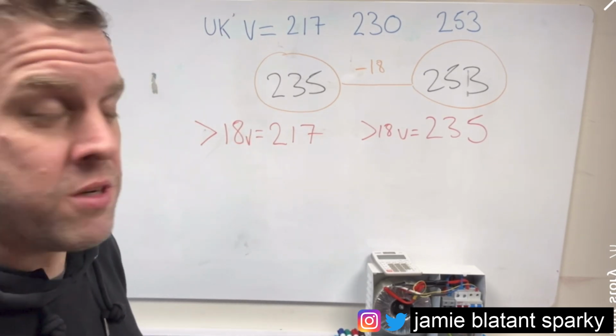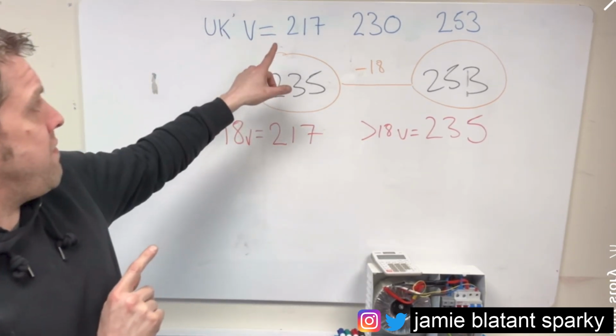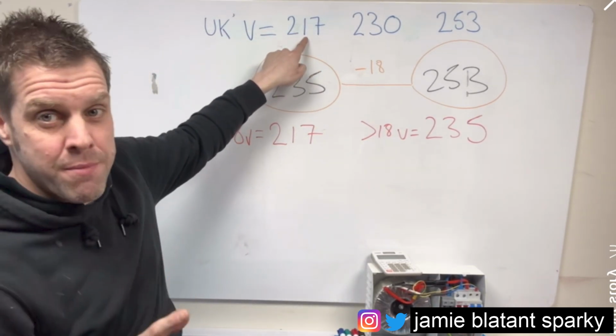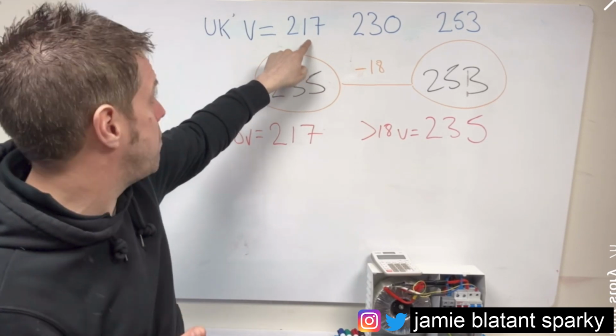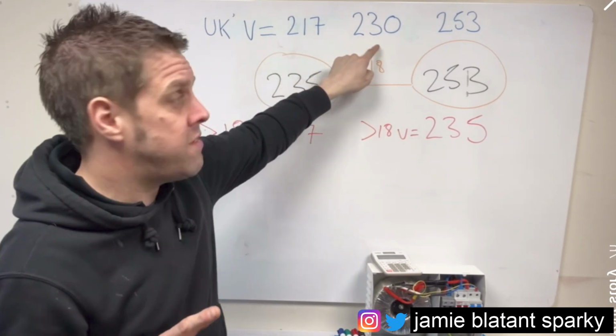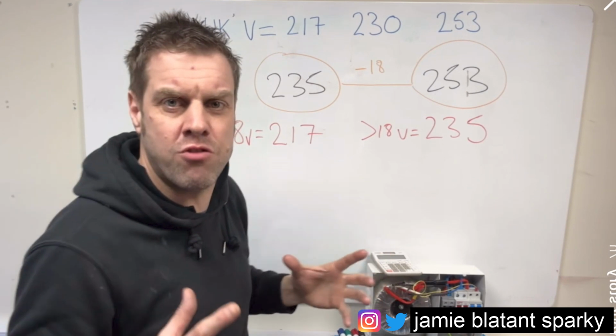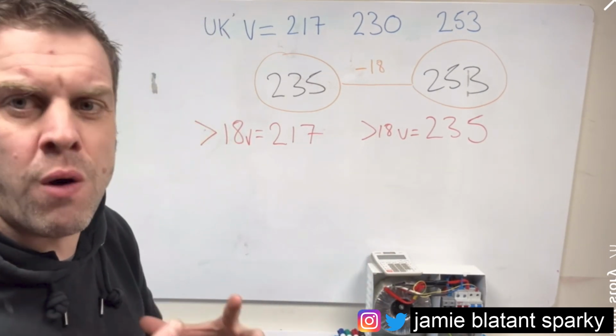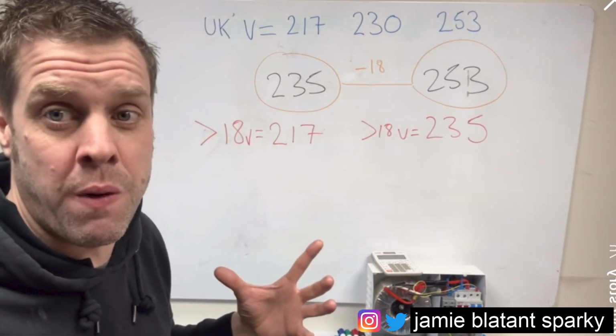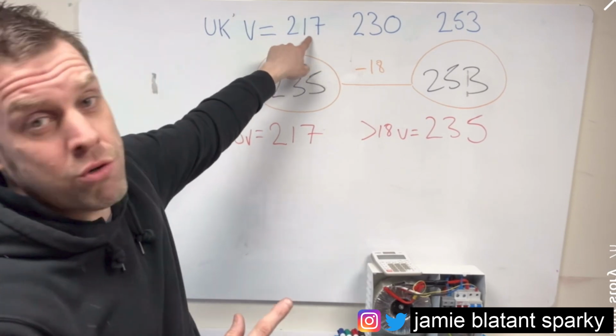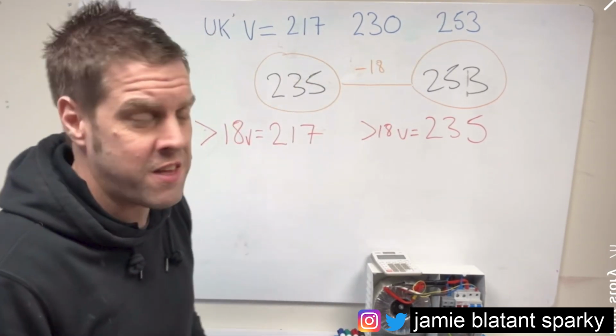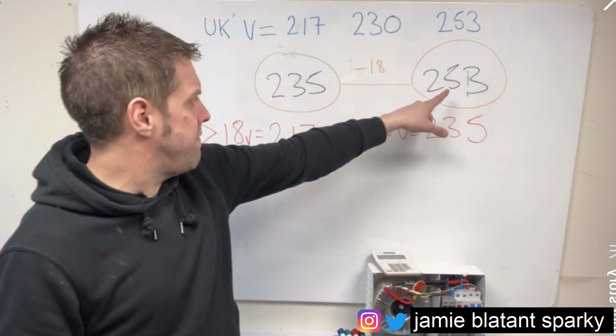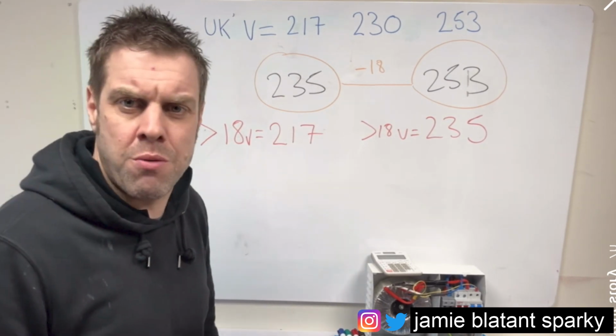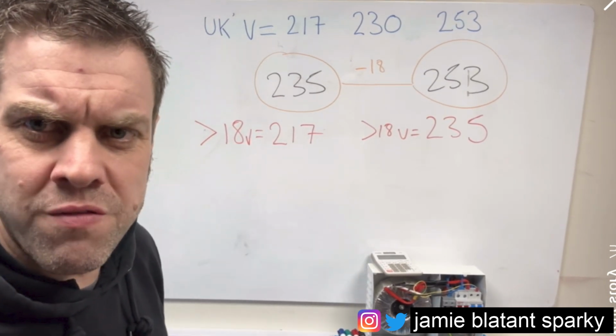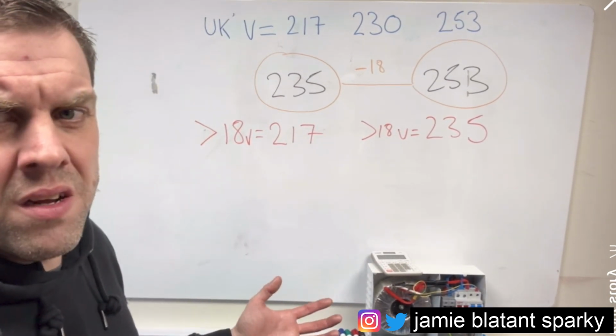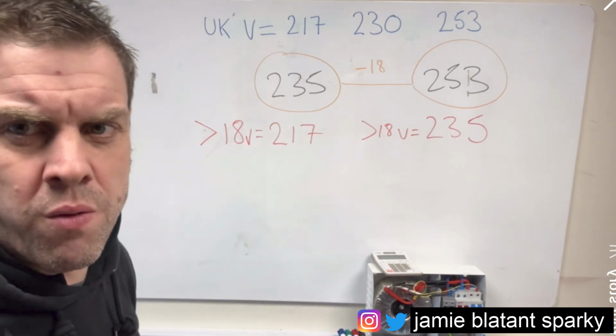Those are very important numbers, because the UK voltage specification is - the minimum it can be in the UK is 217 volts, the ideal is 230, and the maximum is 253. That's the electricity supply regulations - it's got to be between 217 and 253. That's why the voltage optimizer has a maximum usable voltage of 253. Well, hang on, that's no good, is it? That's not optimising my voltage.